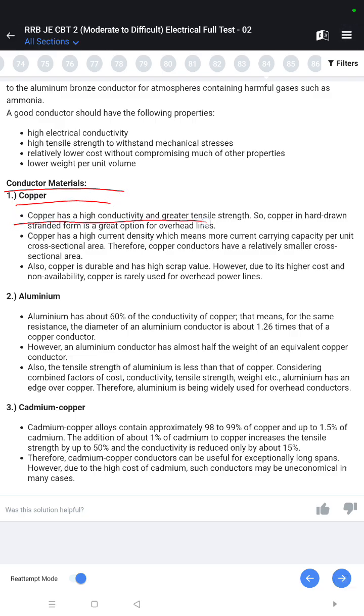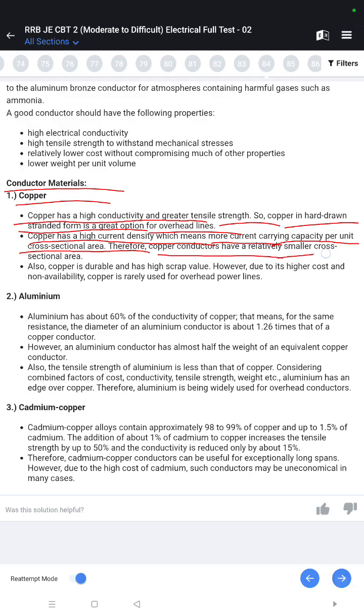फिर देखिए conductor material copper. Copper has high conductivity and greater tensile strength. So copper in hard-drawn stranded form is a great option for overhead lines. Copper has high current density, which means more current carrying capacity per unit cross-sectional area. Therefore, copper conductors have relatively smaller cross-sectional area.